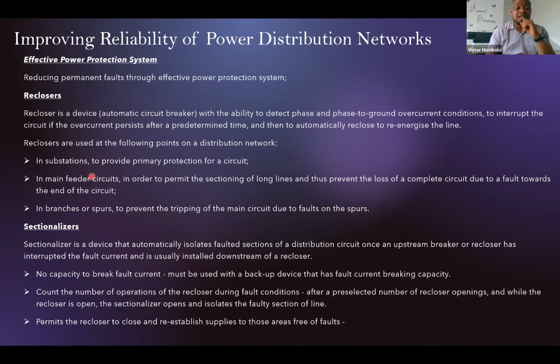What it does is, if there's a fault, especially a transient or temporary fault, it senses that fault, it trips the system temporarily, waits for a few seconds, then tries to re-engage it. If the fault is still there, it drops out again. It does this for a predetermined number of times and for a predetermined duration. And it causes the system to drop the network out, in and out.